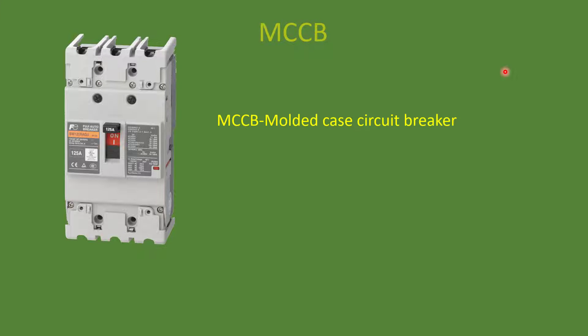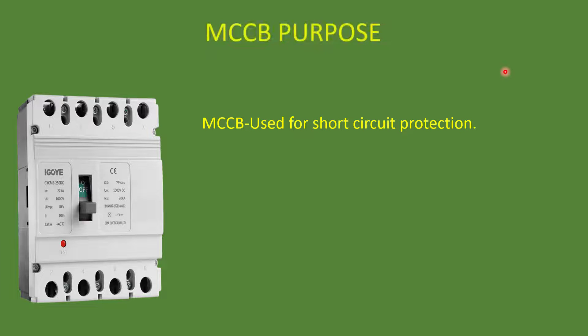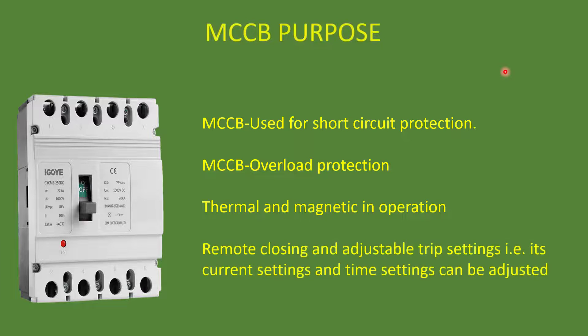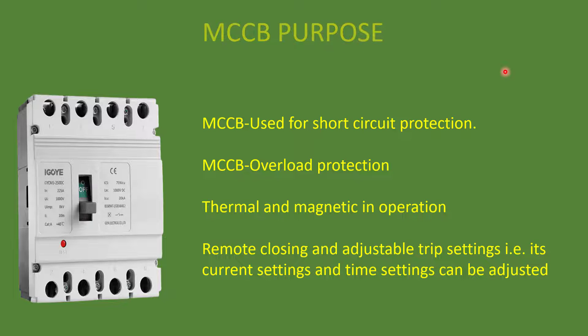Another type of circuit breaker is MCCB — the full form is Molded Case Circuit Breaker. It is used for circuits from 15 to 630 amps. In general cases we do not use MCCB inside our home — it is used in sub-main distribution boards or main distribution boards, more for industrial use. The purpose of MCCB is the same as MCB: it provides short circuit protection as well as overload protection. It is again thermal and magnetic in operation. MCCB is used for slightly higher current applications than MCB.